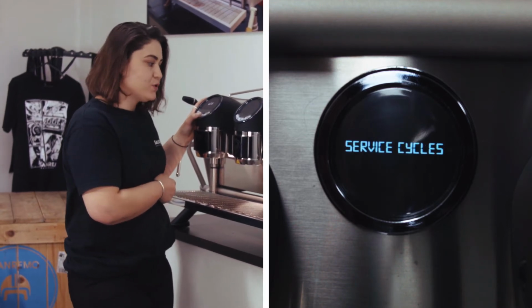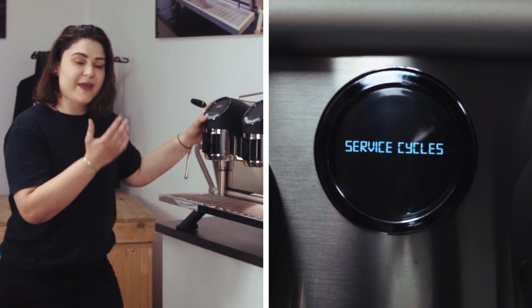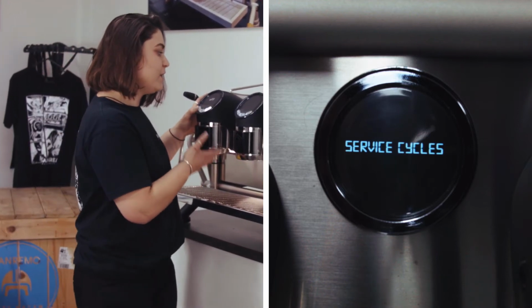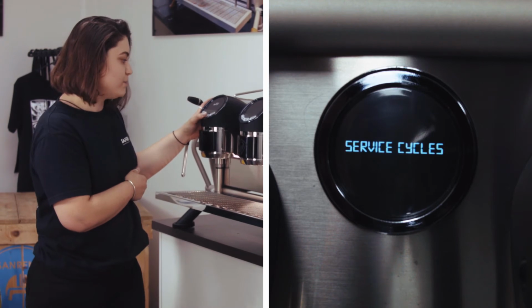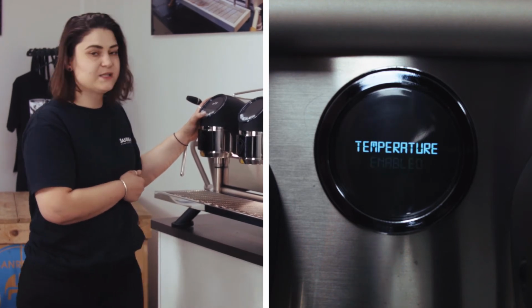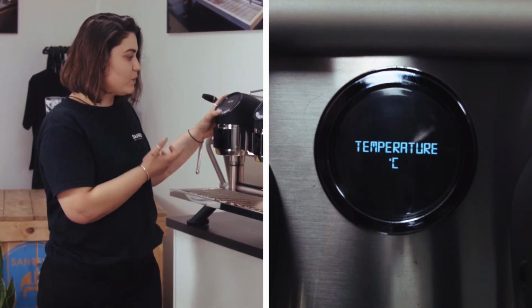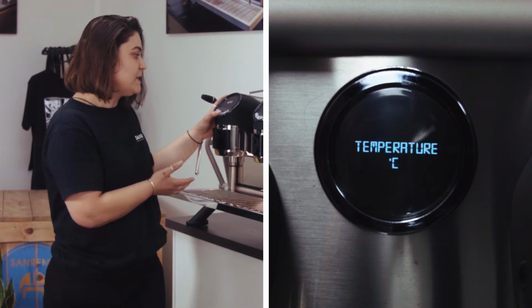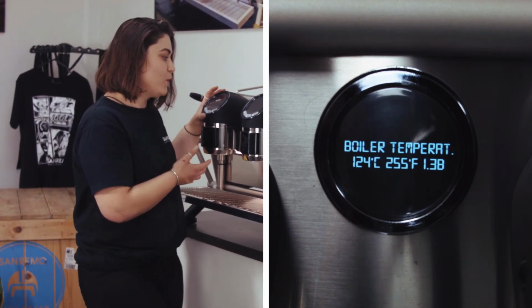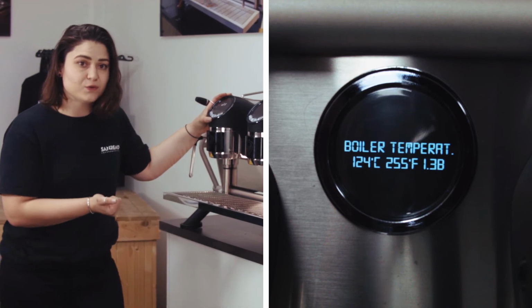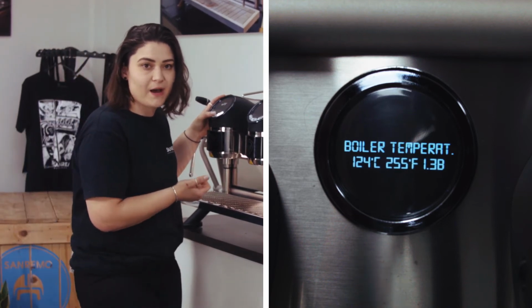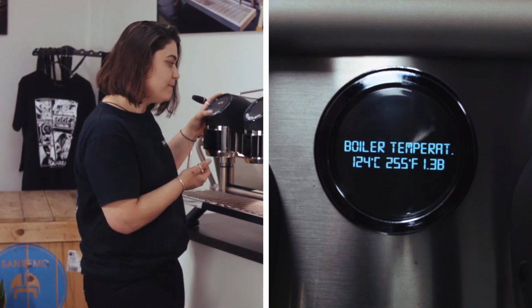Service cycle, you can put a service cycle in the machine, so a countdown. If you choose to, this is how you activate it and put it on. Temperature is enabled, obviously, and we want Celsius because we're here in Australia. Then you have your boiler temp. So you've got 124 degrees and a 1.3 bar pressure on your steam boiler.